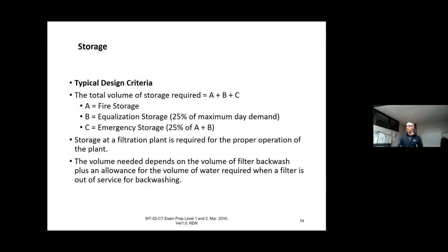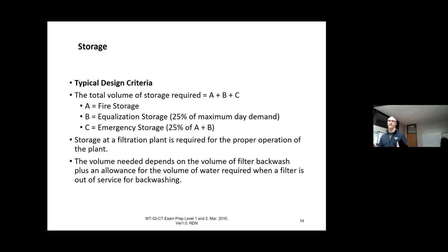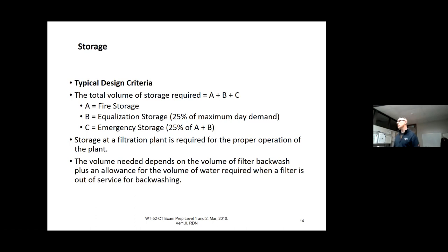How they calculate this is interesting — it's A + B + C. A is fire storage, the number one design criteria. B is equalization at 25% of the maximum day demand — the most water you can put out for that day. C is emergency storage at 25% of A + B. To properly size your storage facility you have to look at all these factors, including volume for filter backwash, because that water comes out of your storage and is part of your demand.